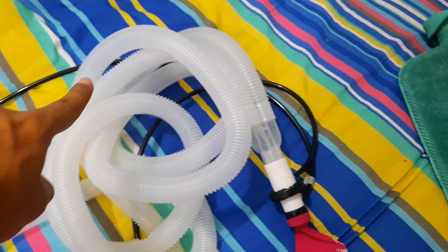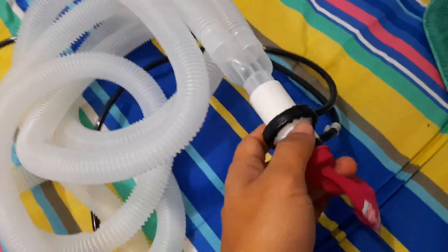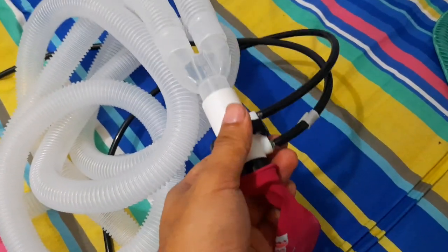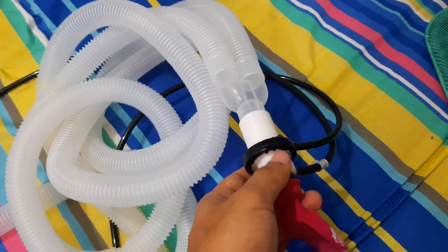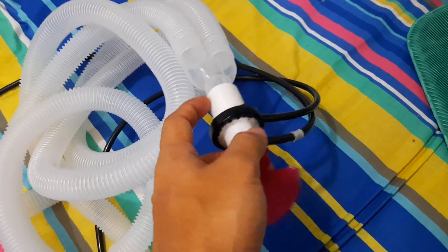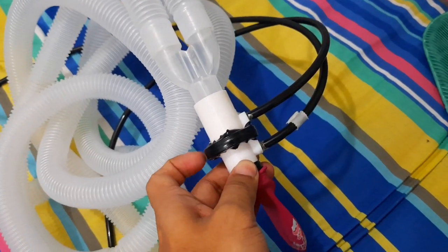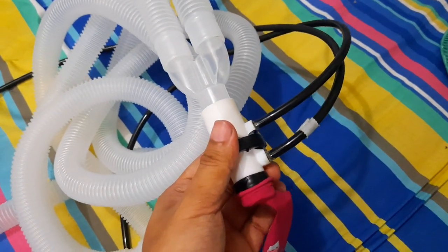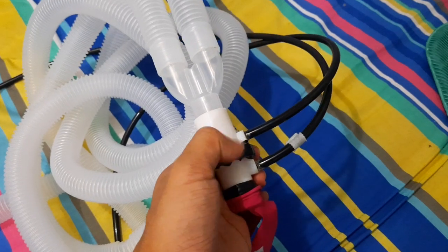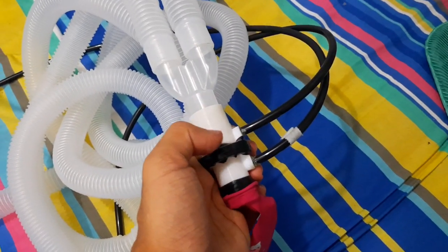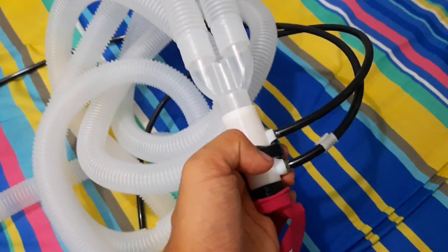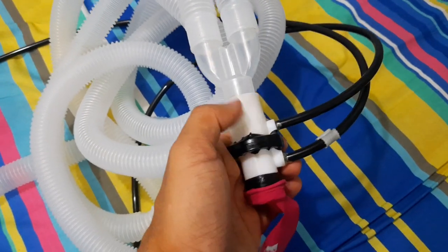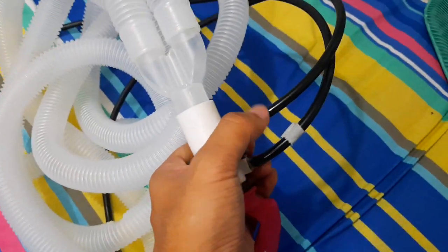This is the patient circuit, and this is the proximal air sensor. It is basically an orifice tube that we have designed to measure air velocity, so that we can integrate over time and find the total volume that has been delivered.